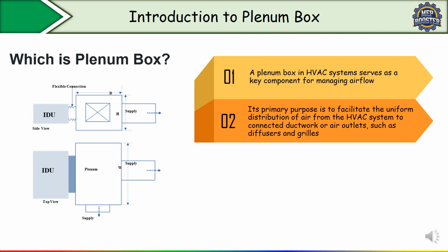So remember, without a plenum box, the airflow from the HVAC unit may be uneven, causing hot or cold spots in a room. By creating a space where air can stabilize, it helps equalize pressure and volume before entering a smaller duct. Correct? And a plenum box also acts as a buffer, reducing noise and vibration from the HVAC unit or fan that might otherwise travel through the ductwork.